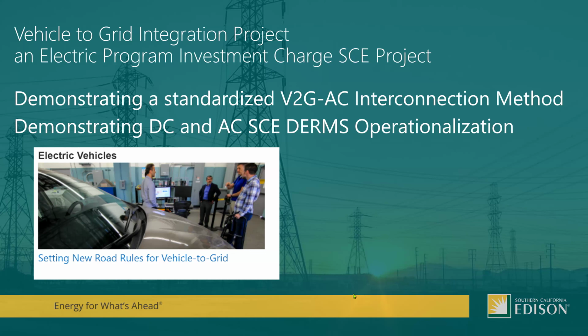The basic premise for the project was the so-called V2G AC model, AC referring to the case where the inverter that interacts with the grid and provides all of those functions is on board the vehicle, in contrast to DC systems where the inverter-based resource is in a fixed position, and that has some implications for things like interconnection and compliance with grid safety and support codes. So that was the original premise of the idea.